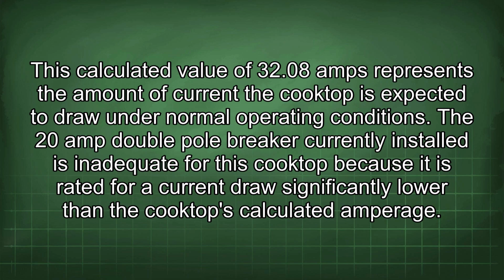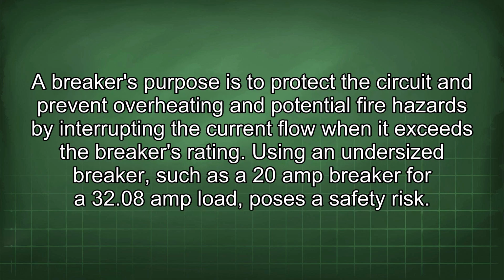conditions. The 20 amp double pole breaker currently installed is inadequate for this cooktop because it is rated for a current draw significantly lower than the cooktop's calculated amperage. A breaker's purpose is to protect the circuit and prevent overheating and potential fire hazards by interrupting the current flow when it exceeds the breaker's rating.